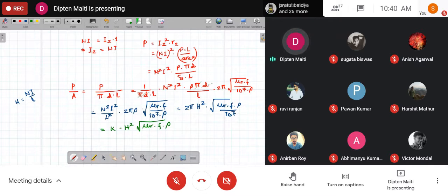To give you some idea, at let's say 500 hertz to 1 kilohertz, that can be of the order of, let's say, 50 kilowatt, so a bit smaller. However, for further higher frequency, when the frequency goes to the megahertz range, the heating capacity of the furnace also increases.